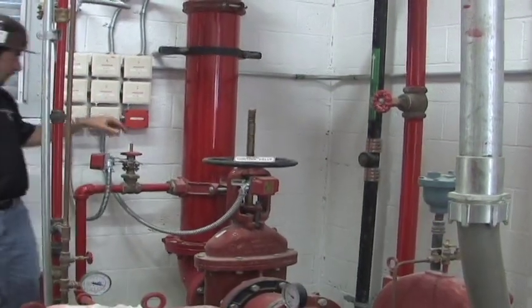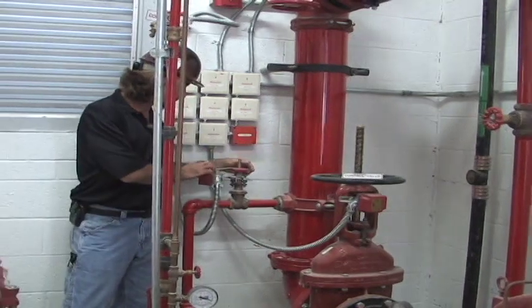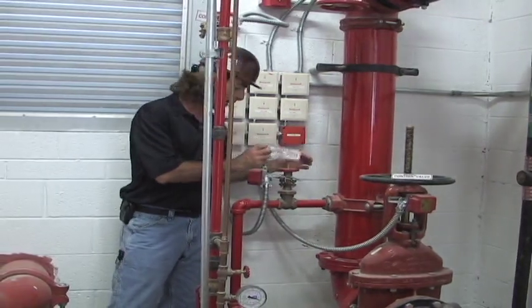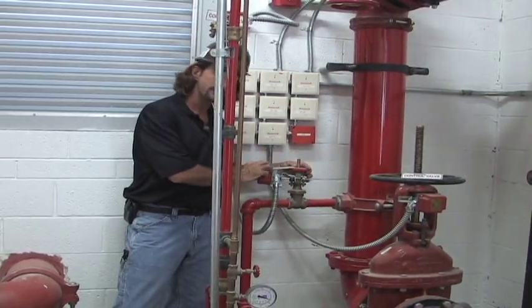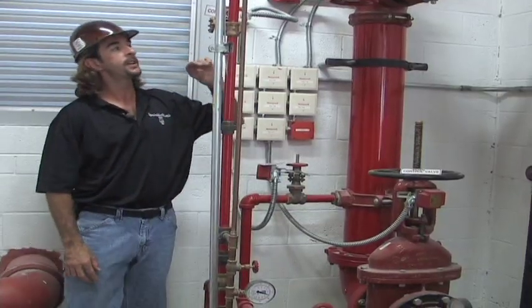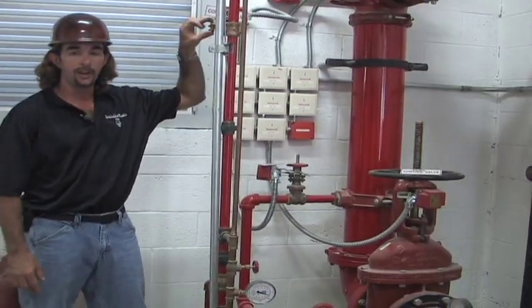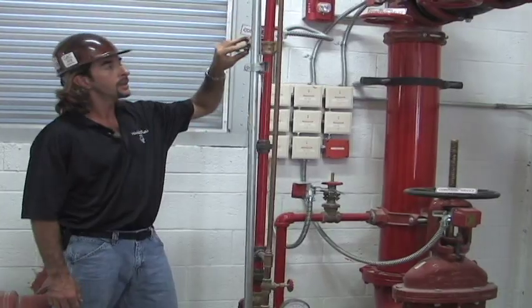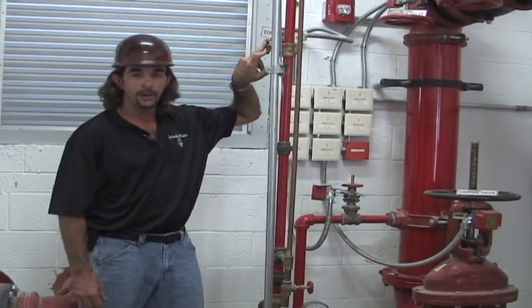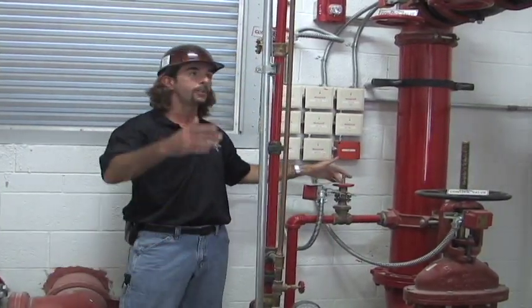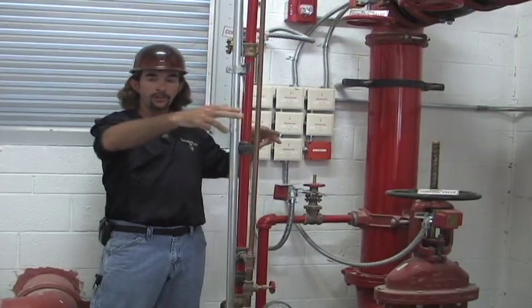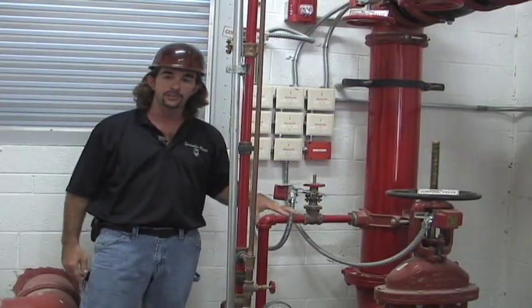On our Jockey pump, coming right off the underground, we also have our Jockey pump supply valve. It's an OS&Y valve. Also, just like the electric fire pump, we have a discharge valve for our Jockey pump. To work on any bit of the fire pump or the Jockey pump, we would close our supply and our discharge to both of our pumps to do any work or any service on the fire pump.